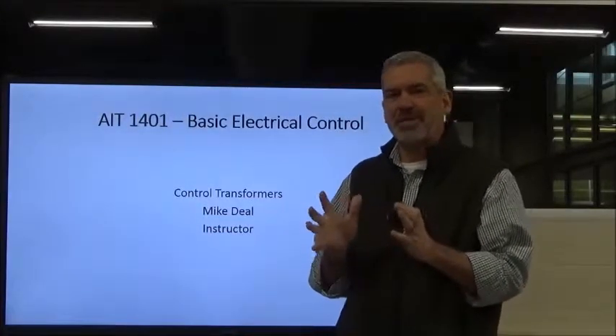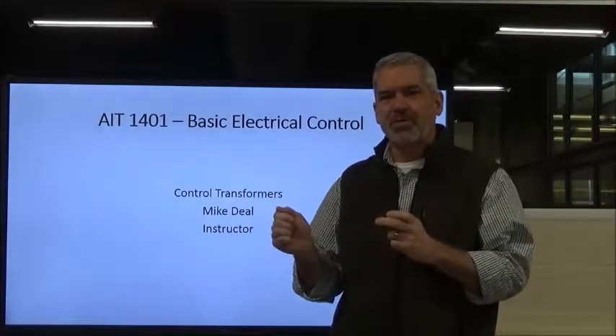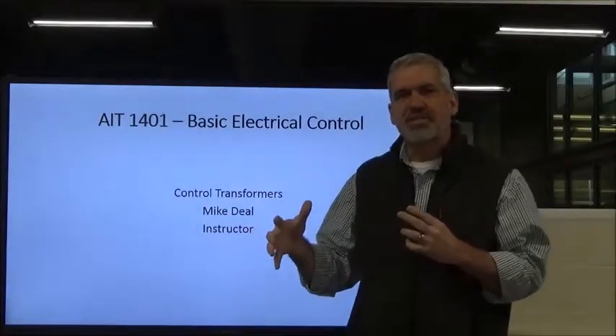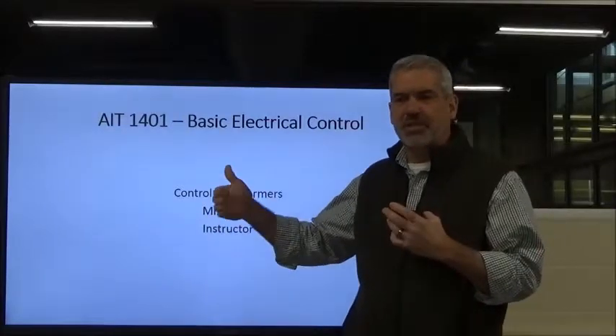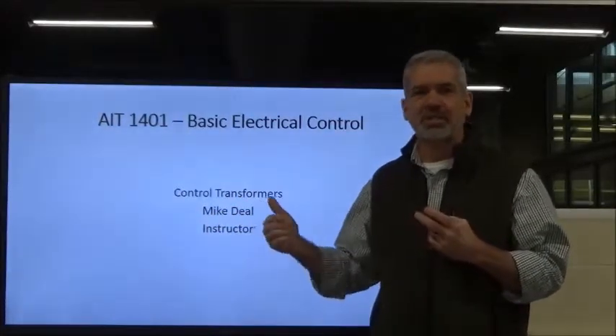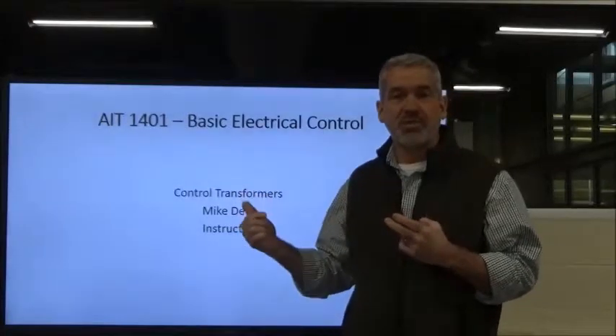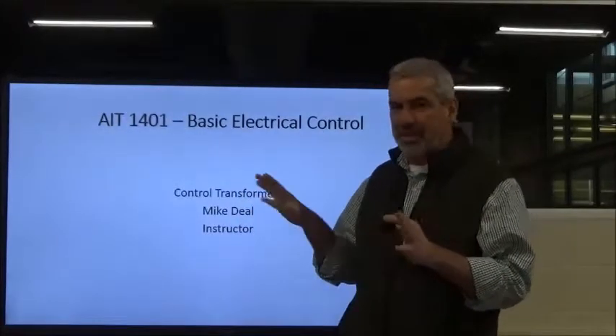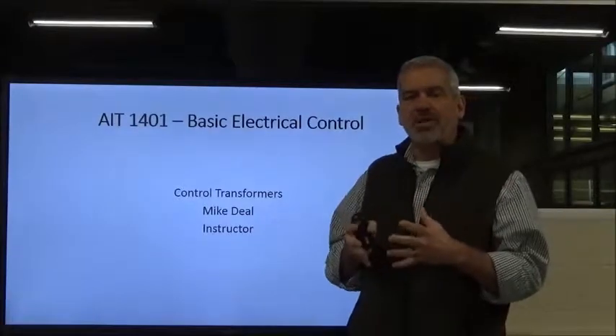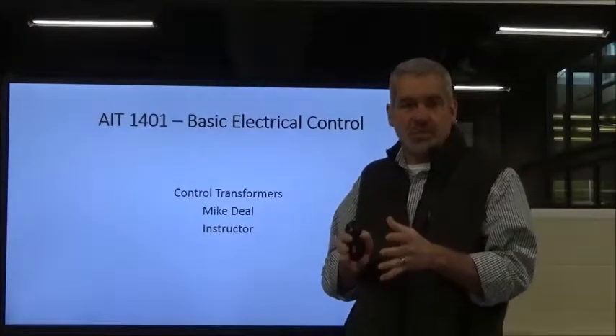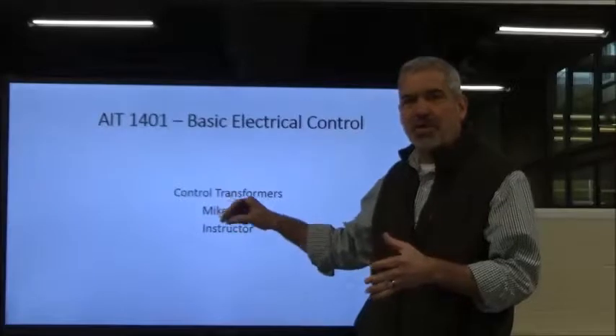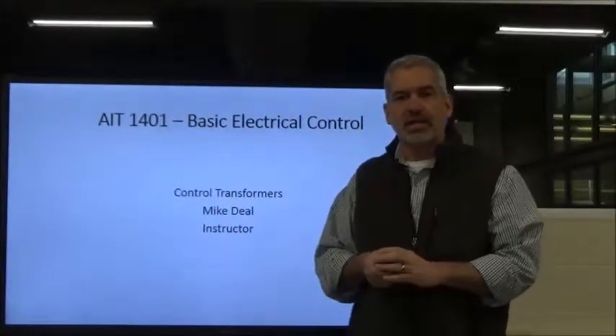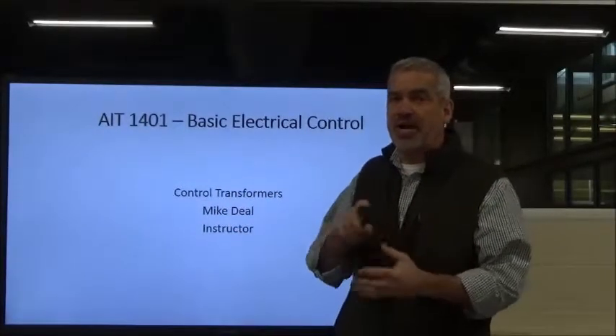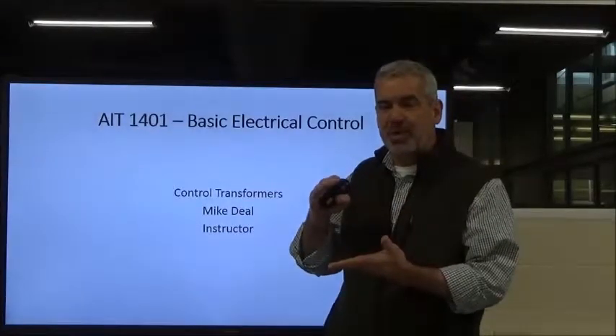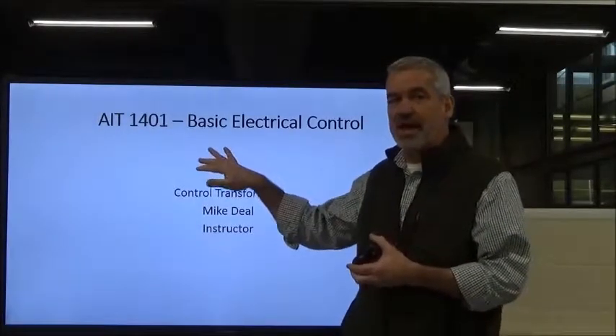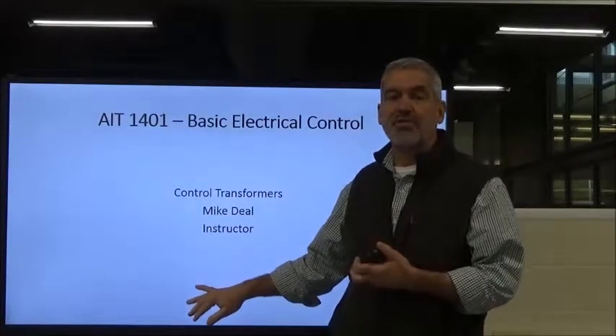So far, we are building a motor control system. We started out with our three-phase system, with three phases of voltage coming into a disconnect, our circuit protection for short circuits, and also for overload protection, and also our motor controller. We did all that. Now we're making our way toward a basic control system. We talked about the power or the motor circuit. Now we're going to move toward the control circuit, but before we do that, we've got to cover an area in between, and that is the transformer that steps down the high voltage from our power circuit down to a lower, safer control circuit.